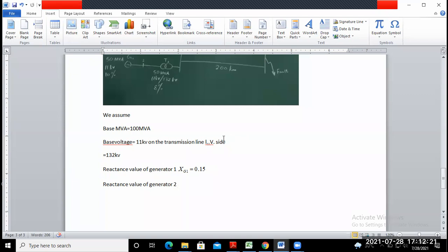Suppose you put this formula in; the reactance value of the generator changes. What is the value given to you here? 10% is given to you for which base? 50 MVA and 11 kilovolt. So this value changes for the base value of 100 MVA and 11 kilovolt, since the base MVA changes. This 10% is given on the basis of base MVA of 50. Now we consider the base MVA 100 MVA, so this value is changing.